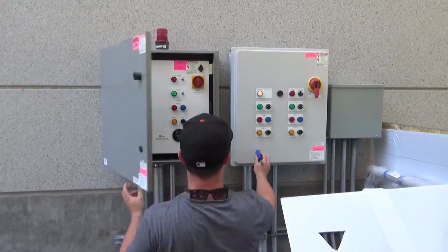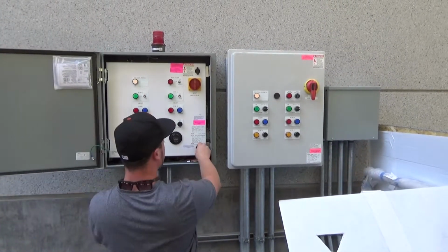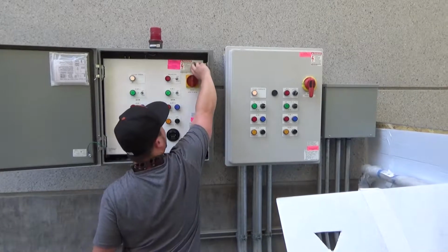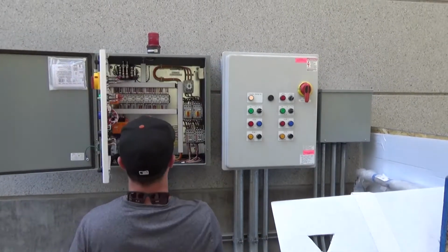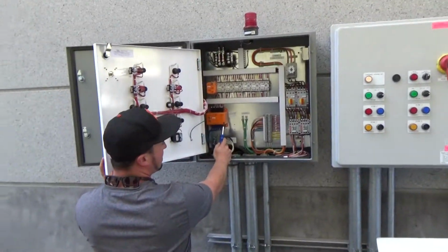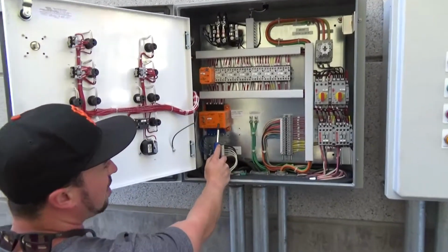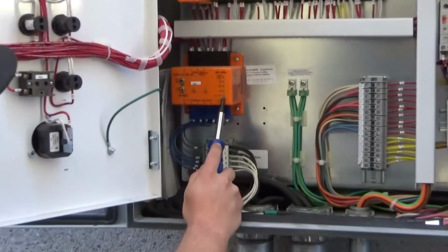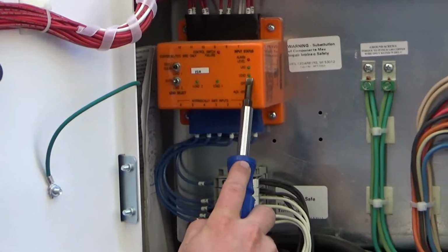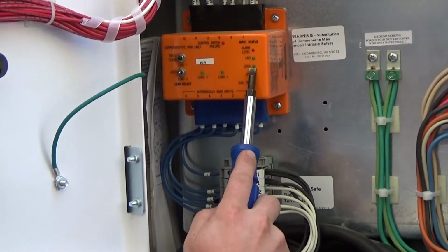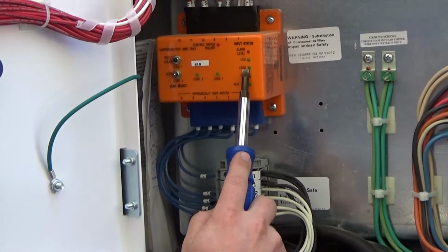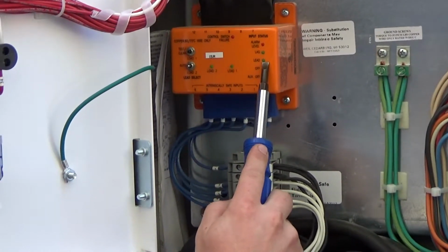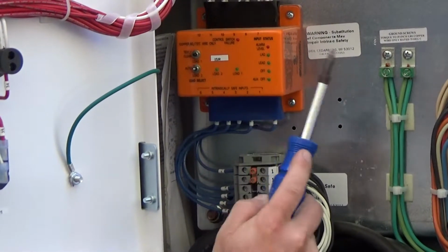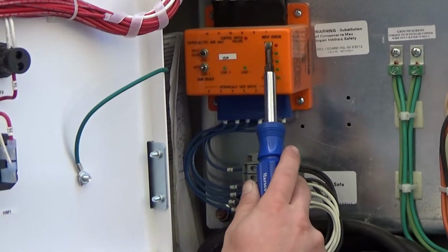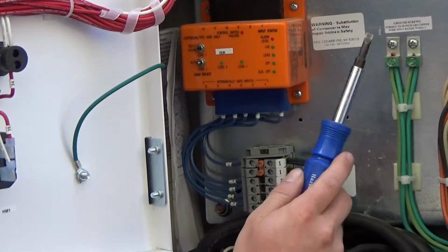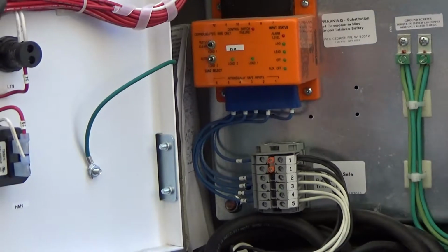Like I said, these 2 panels are different. So this one doesn't have a sequencer inside, so it doesn't tell you which floats are made and which aren't. This one does. So what's going to happen is that pit's going to fill up. You'll see auxiliary, off, and off make. Okay, so these will light up. Nothing's going to happen. As soon as this one lights up, the lead pump will kick on, and he'll keep pumping. You'll see him disappear. It'll keep pumping until these break, and then the pump will shut off. But pretty much this is just a status alarm, the status bar of what's happening in terms of that pit.